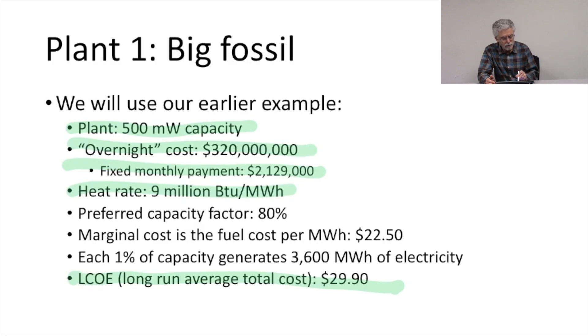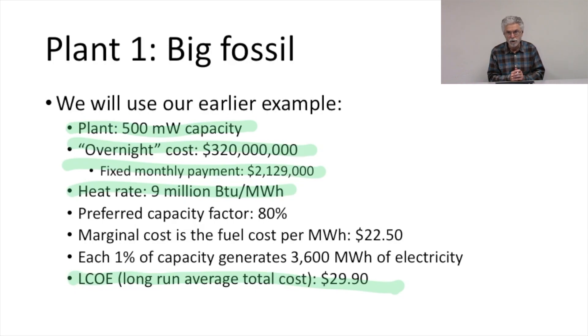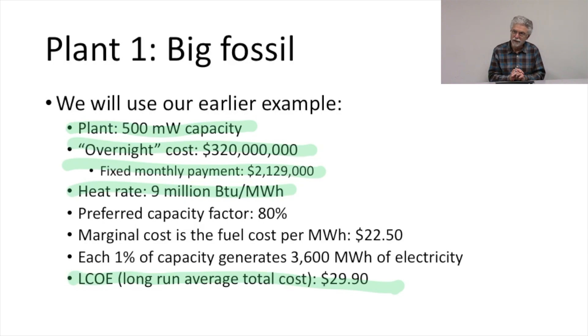The heat rate is assumed to be 9 million BTU per megawatt hour. I'm making these numbers up, so I'm not saying this is exactly like any power plant you know, but we're assuming a heat rate of 9 million BTU per megawatt hour for our fossil power plant, and a preferred capacity factor of 80%. Could be 70%, could be 85%, but in this case we're assuming a capacity factor of 80%.